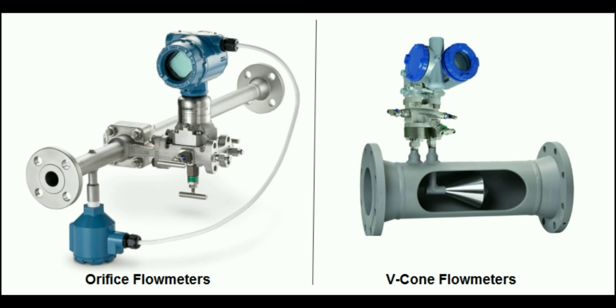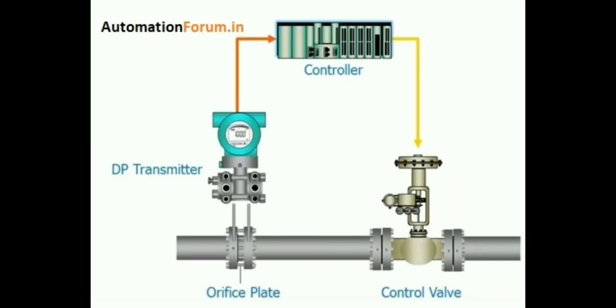Across the obstruction, resulting in a higher differential pressure measured by the transmitter. The DP flow transmitter consists of a sensing element such as a diaphragm or strain gauge that measures the pressure difference between the two pressure taps connected to the pipeline, which may be an orifice plate or a venturi tube. The transmitter converts the differential pressure signal into a standardized output signal like 4 to 20 milliamps or 1 to 5 volts, which is proportional to the flow rate and can be transmitted to a control system such as a PLC, DCS, or PID controller.